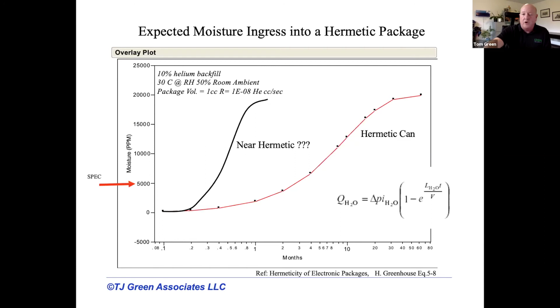Now fortunately, based on my experience, when it comes to hermeticity it's usually all or nothing. You either get a great seal and it's way down in the mud as far as a leak rate, or you have what we call a fine leaker. Those are the ones you're worried about, but thankfully they don't occur as often. But when they do, it's a big worry, and that's what you have to worry about when you set your specs.